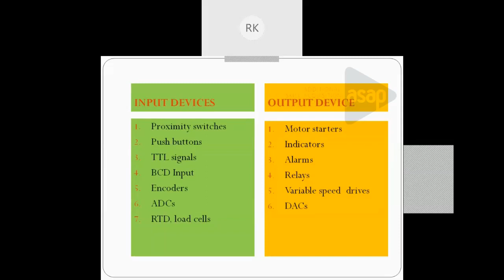So you can see this is the operation, or the execution cycle, of a PLC. The controller always monitors the inputs. It takes the input from the input devices and accordingly executes the program. According to the input changes, the program also changes. It executes the program, communicates with the environment, and correspondingly updates the output. The whole cycle we call one scan. Depending on this scan time, we define the operating speed of the PLC.